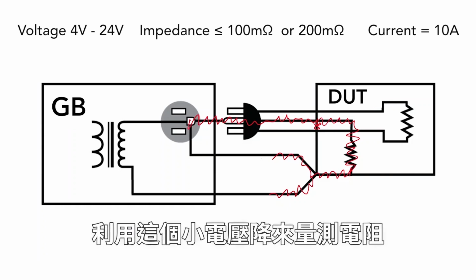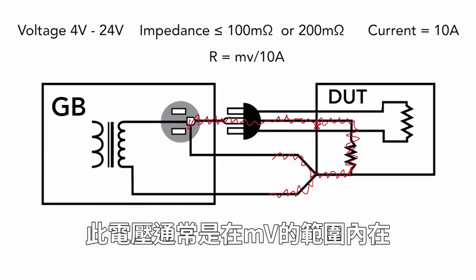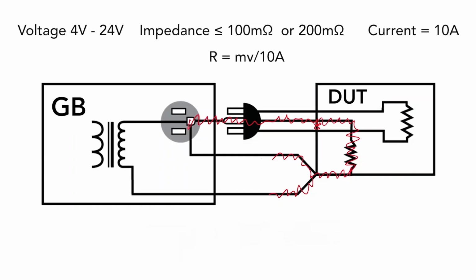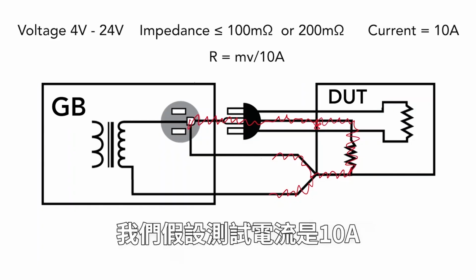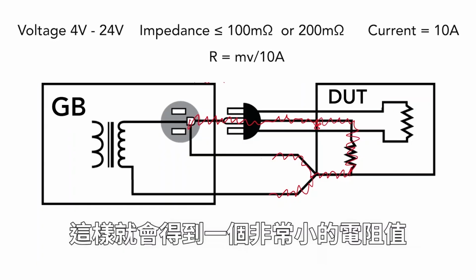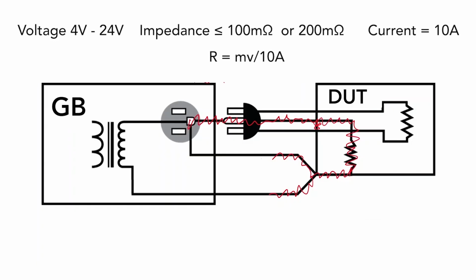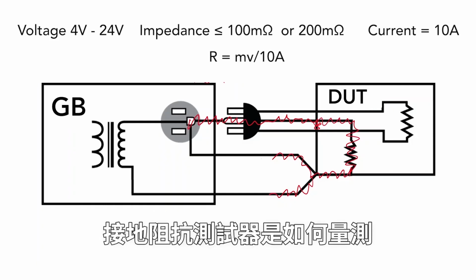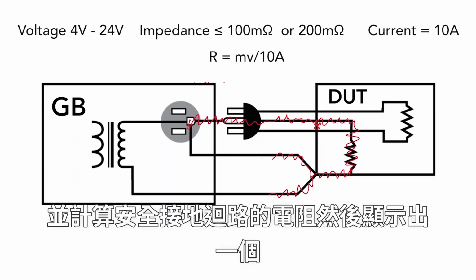So the resistance can be measured using the small voltage drop, which is usually in the millivolts range, divided by, for example, let's pick 10 amps for our current. This will result in a very small resistance value. That's how the ground bond tester measures and calculates the resistance of the safety ground circuit and displays a milliohm number.